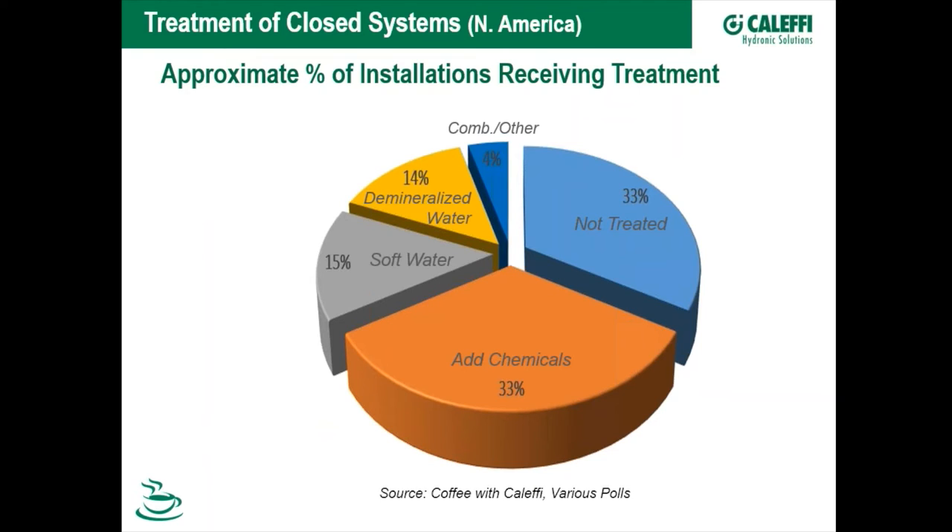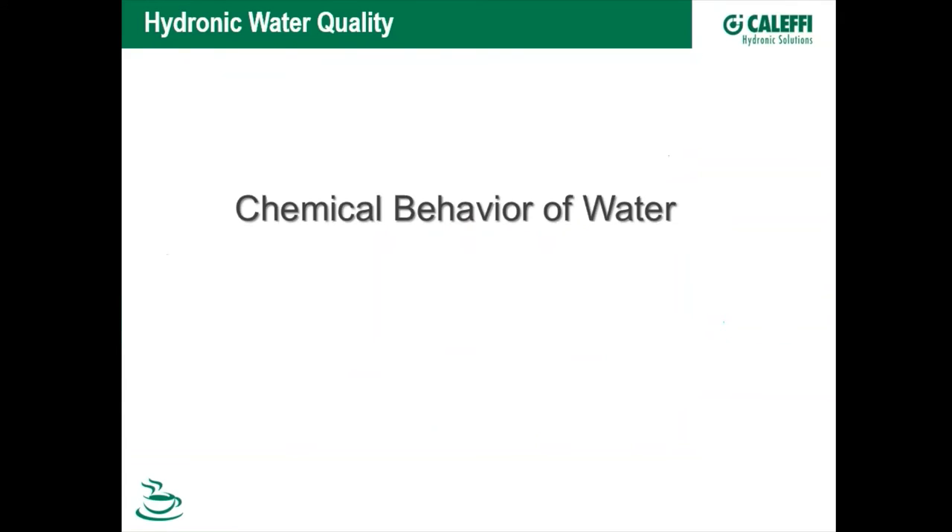In North America — US and Canada — based on Coffee with Caleffi polls and other input, about one-third of all systems have no treatment at all: water from the site goes straight into the system. Another third has some chemical added — glycol, a buffering agent, or an oxidizer. The remaining third is split between systems filled with softened water and systems filled with demineralized water, which we consider the best form of treatment. I'll come back to this slide at the end of the webinar with recommendations.